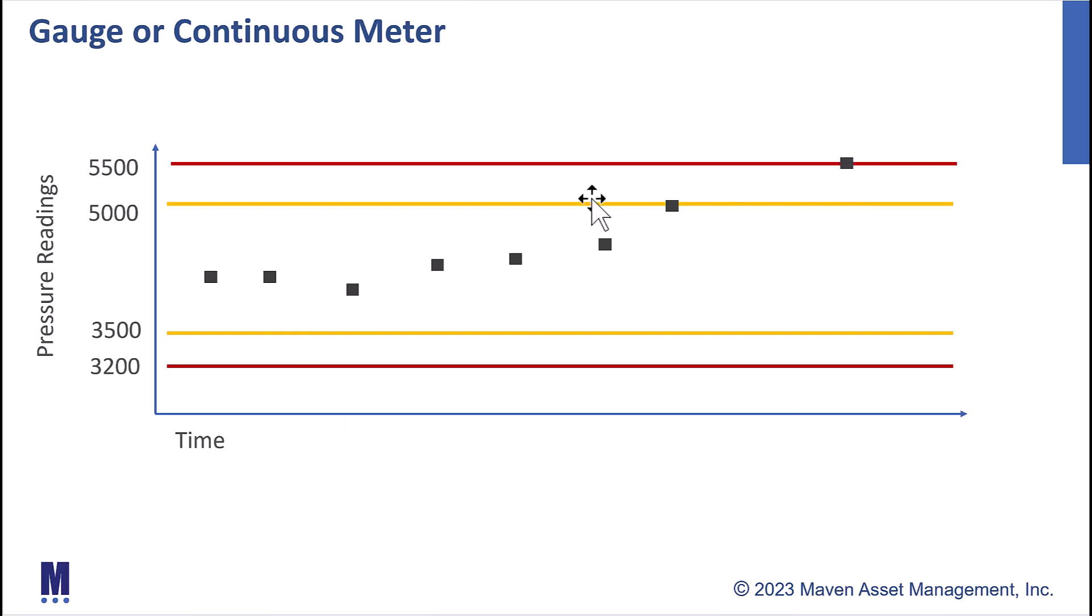Using Maximo, we want to monitor or we want to automate that, and we can do that with a condition monitoring application. We basically set up a point on this particular meter for the asset, which is known here. We identify our upper and lower control limits as shown here, and then if we enable the Maximo cron task to automate work orders based on those values, when we hit this value, Maximo will automatically generate the specified work order or job plan on the work order for our action.